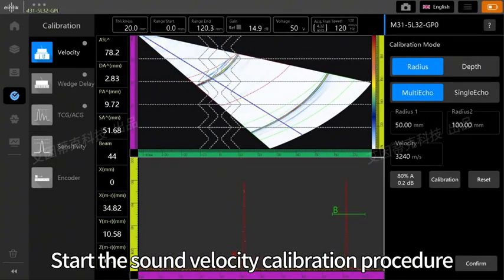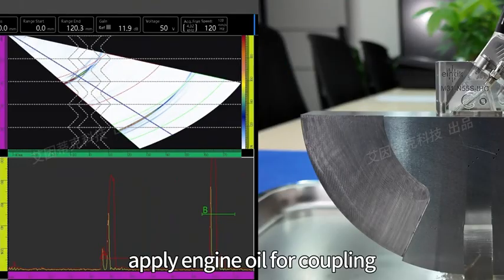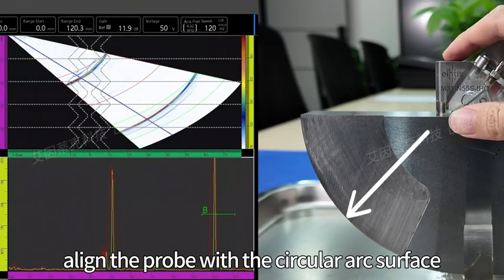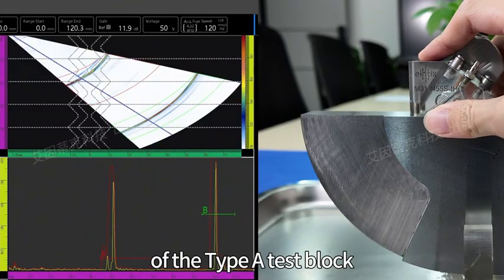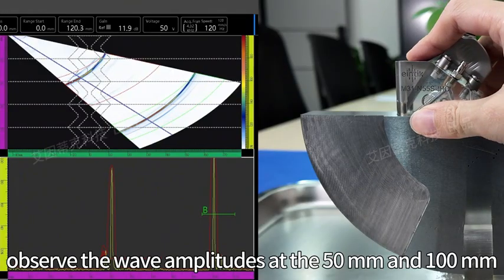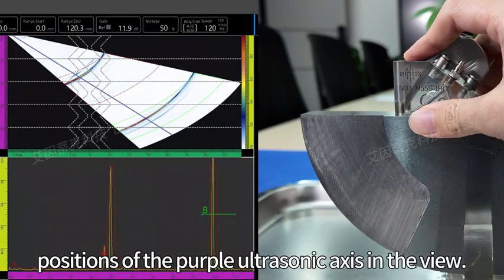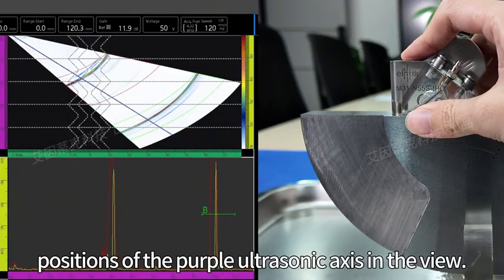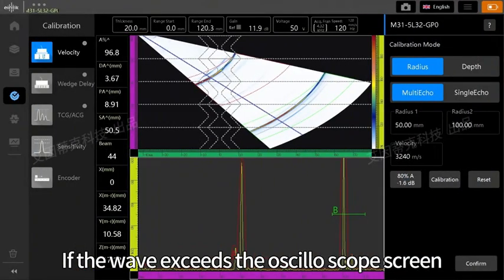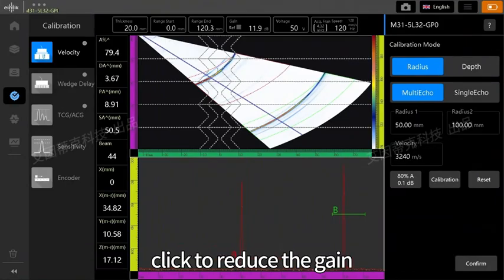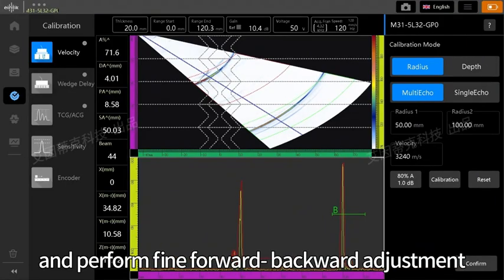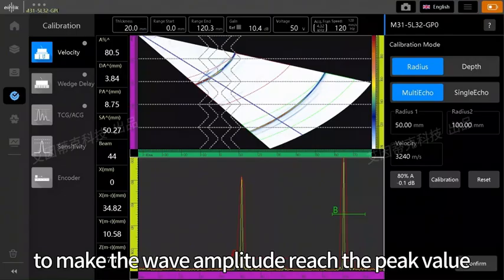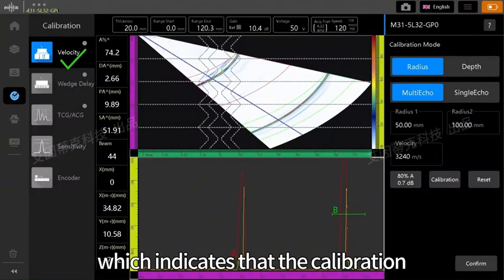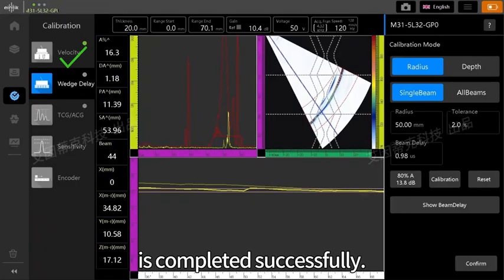Start the sound velocity calibration procedure. Apply engine oil for coupling. Align the probe with the circular arc surface of the Type A test block. Observe the wave amplitudes at the 50 mm and 100 mm positions of the purple ultrasonic axis in the view. If the wave exceeds the oscilloscope screen, click to reduce the gain and perform fine forward-backward adjustment to make the wave amplitude reach the peak value, which indicates that the calibration is completed successfully.